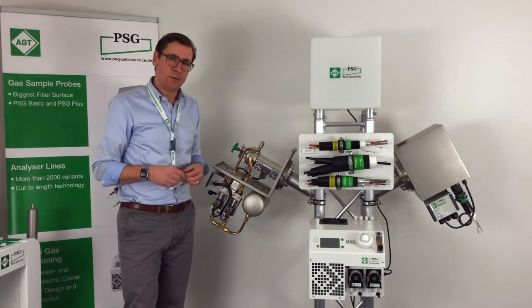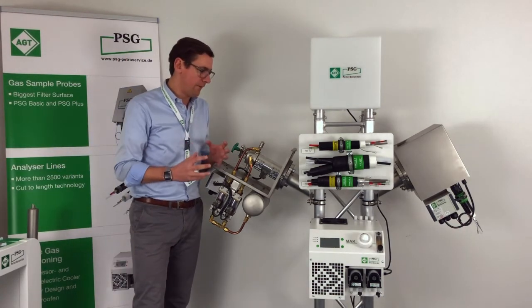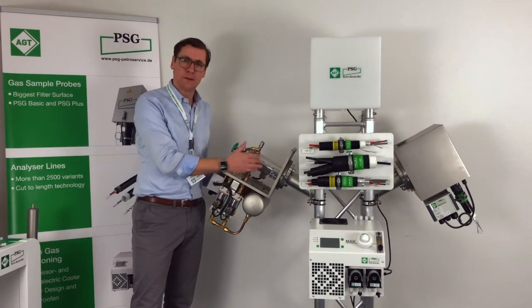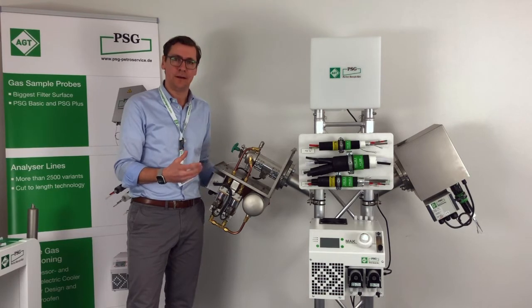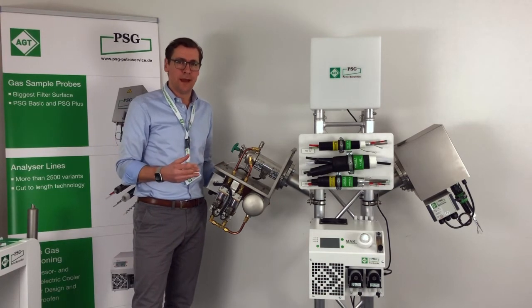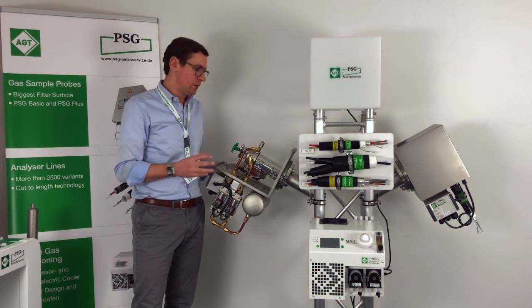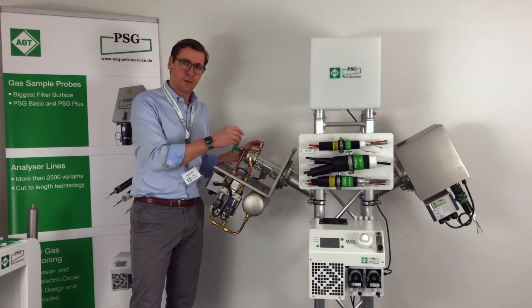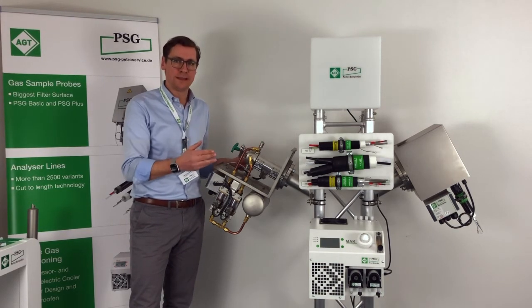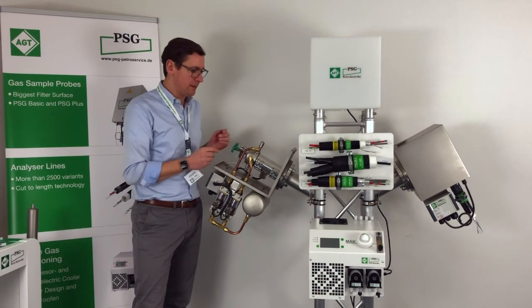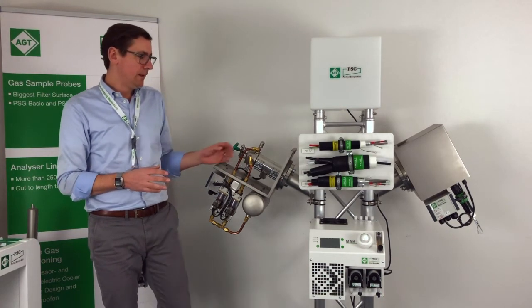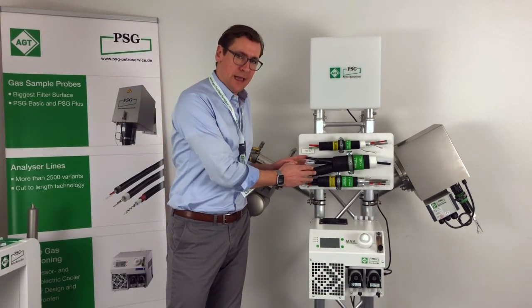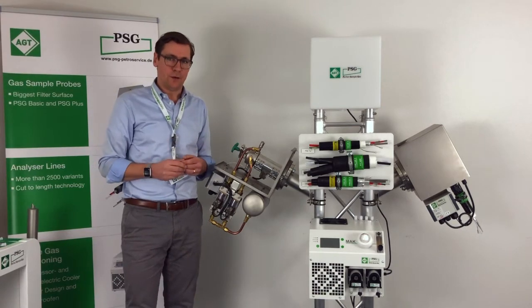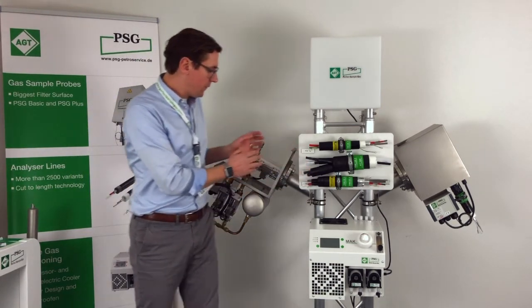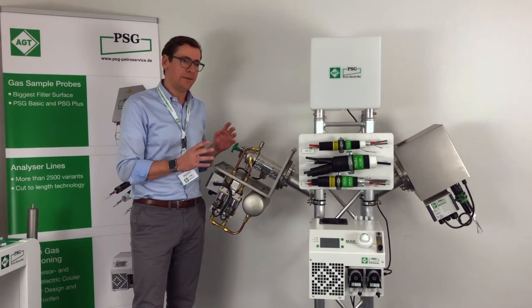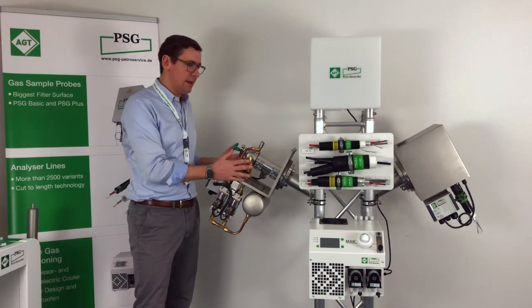This is a big advantage because it allows a very dry instrument air to be purged into the probe, and the instrument air is preheated. Sometimes you will find non-preheated solutions, which, at the moment the instrument air is purged into the probe, will result in a temperature drop, which might give you condensation problems. So the PSG Hybrid Line, where we also offer different options, can be used to fully operate the probe without having any additional installation needed at the probe.